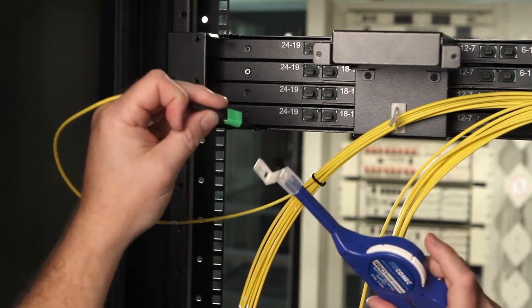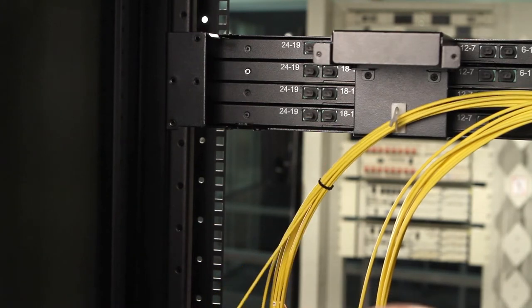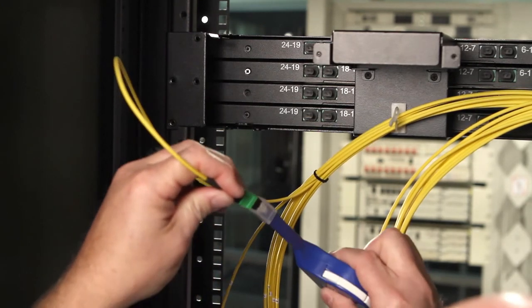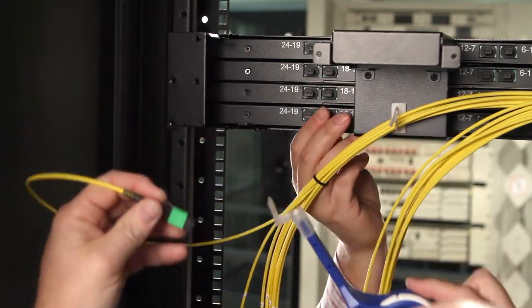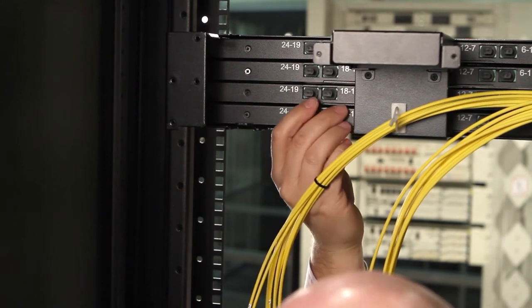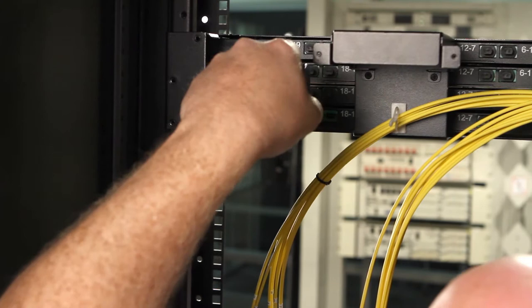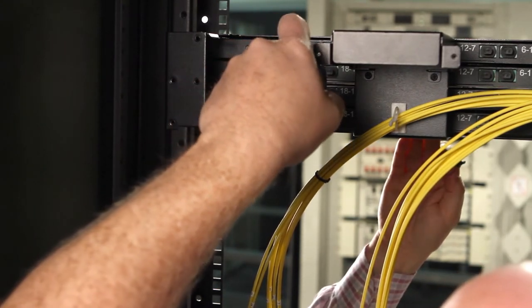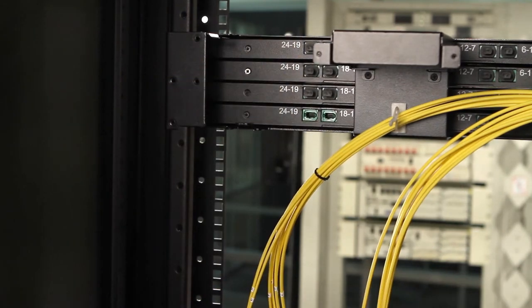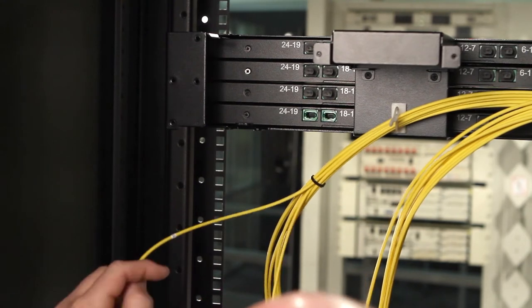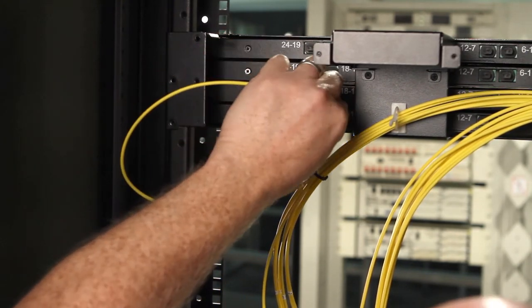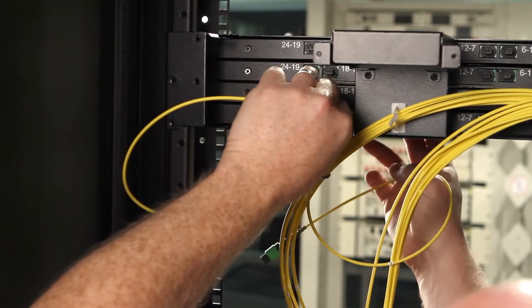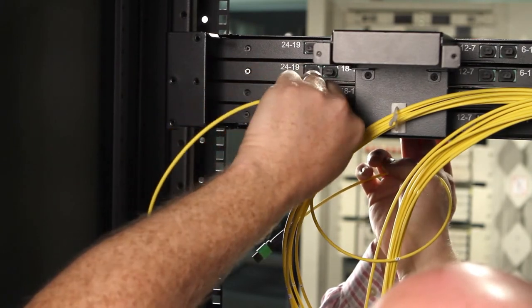Clean the surface of each MPO and then also clean the individual ports. Tail 15 will go to the inside toward the center of the chassis. We're forming a nice loop.